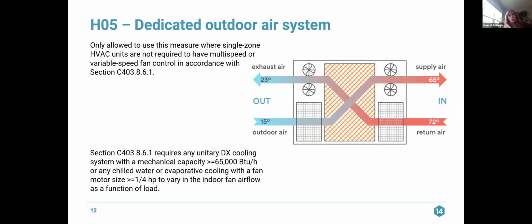look and see if you are required to have a variable speed fan in accordance with section C403.8.6.1. Section C403.8.6.1 requires that any unitary DX cooling system with a mechanical capacity greater than or equal to 65,000 BTUs, or any chilled water or evaporative cooling with a fan motor size greater than or equal to 1/4 horsepower, to vary the indoor fan airflow as a function of load.